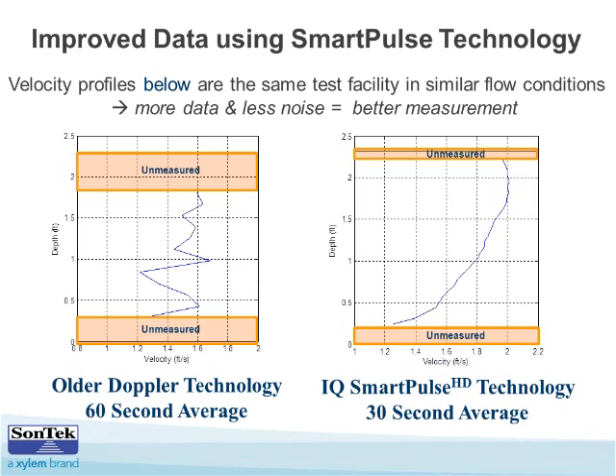And one of the reasons why is that this thing is sampling at a much higher frequency than the older systems, potentially up to somewhere between 60 and 70 hertz. What this affords you and buys you, though, is that where the older Argonaut technology was pretty tough to use for control, especially if you wanted to make some quick control adjustments, say on a gate or something, with 30-second averages now, this thing lends itself more to being used in a control application, as well as real-time monitoring. Right. One thing I did want to hit on is this word SmartPulse.